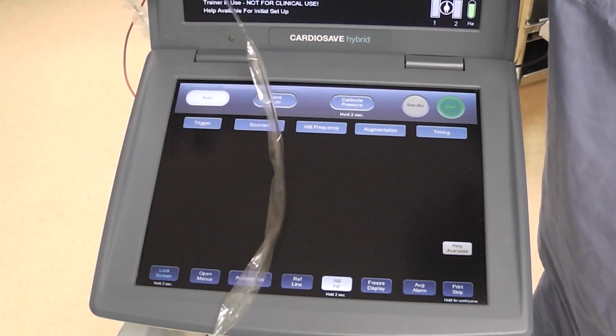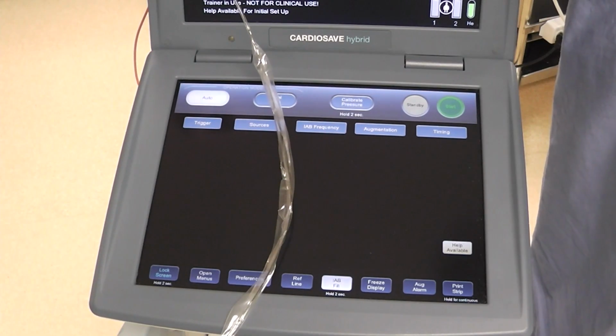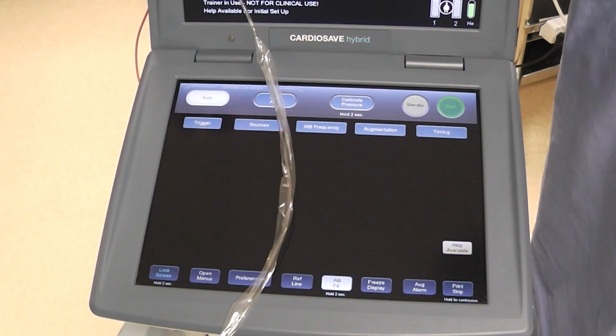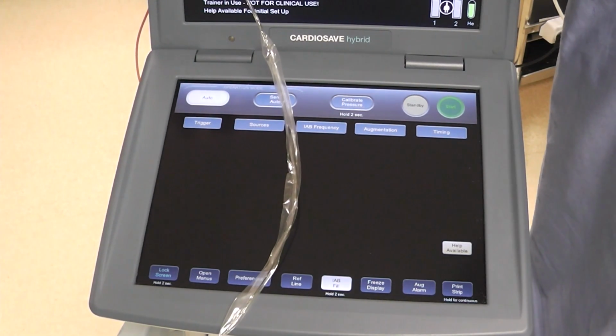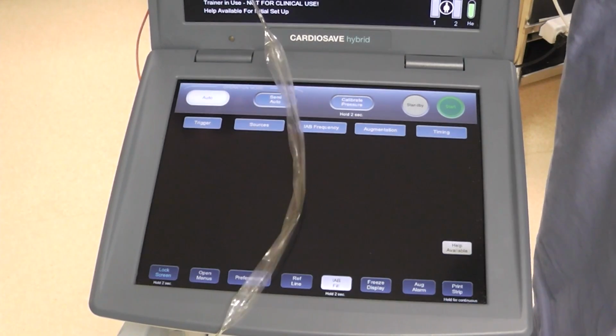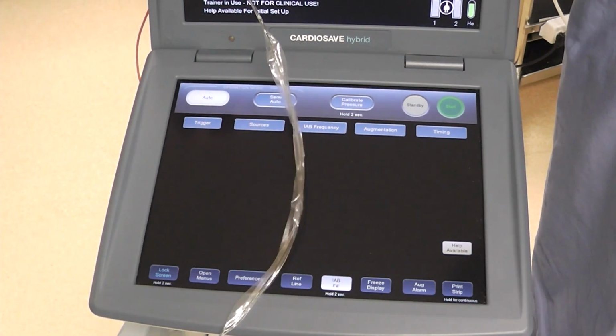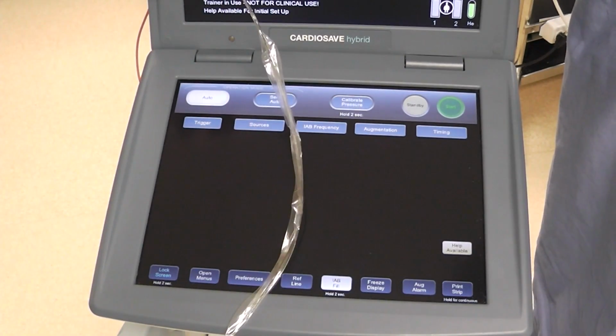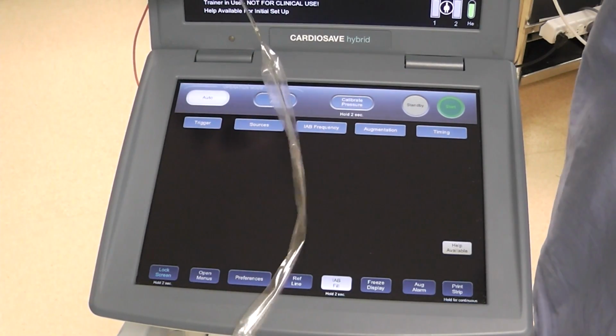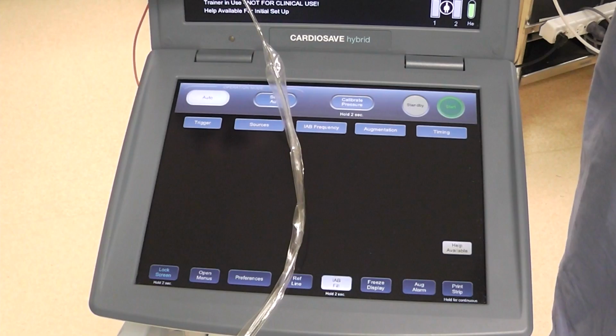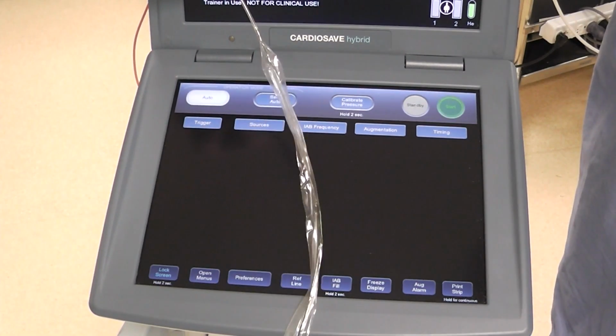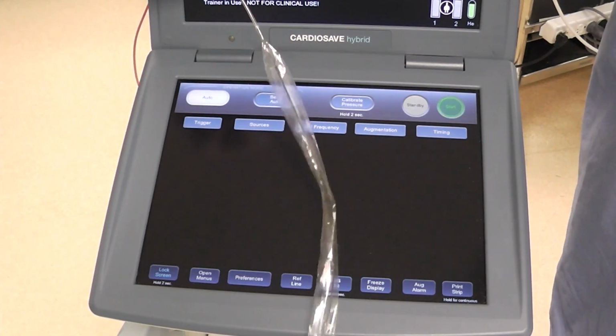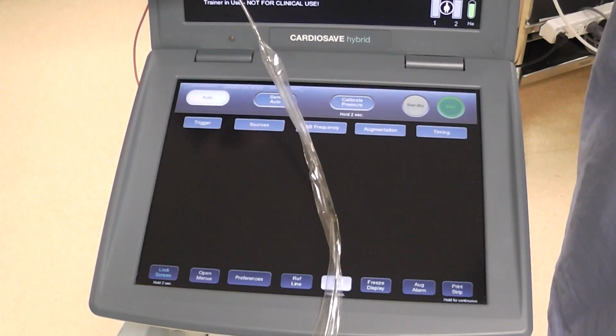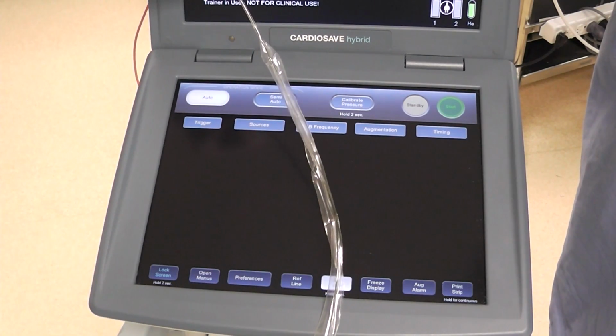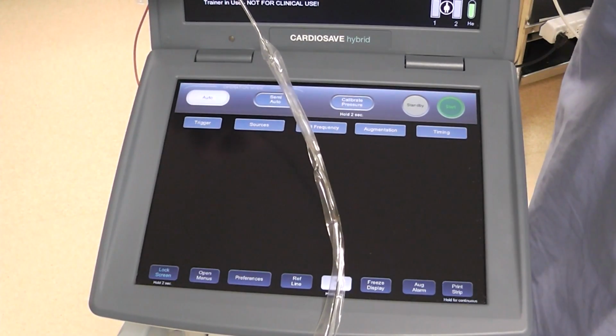Now what it'll do, I have the catheter here, is it'll actually do a couple of autofills, as you can see. The purpose of that is to fill the balloon and verify that the amount of helium that the console is sending to the balloon is the amount that it's getting back, just to make sure that there are no leaks. Once that has completed, now you can see it will start pumping. And you will see it pause here as well. Now it's kind of paused, and that's sort of to verify the auto settings.